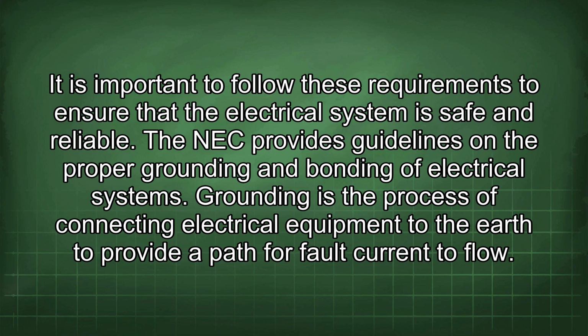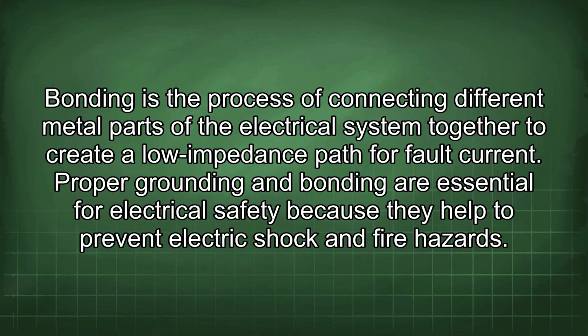The NEC provides guidelines on the proper grounding and bonding of electrical systems. Grounding is the process of connecting electrical equipment to the earth to provide a path for fault current to flow. Bonding is the process of connecting different metal parts of the electrical system together to create a low impedance path for fault current.